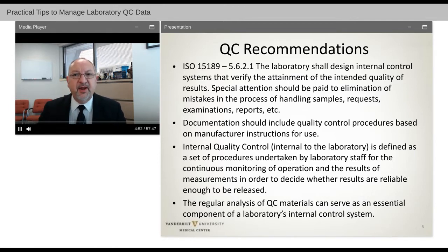Internal quality control, by this definition, is that liquid QC, those processes and analyses that we do in the laboratory that are internal to our laboratory, as opposed to proficiency testing, which I'll describe later in this talk. Internal quality control is defined as that set of procedures undertaken by the laboratory staff for the continuous monitoring of operation and the results of measurements in order to decide whether we release results and whether they're reliable enough for patient care. The regular analysis of quality control materials serves as an essential component of our laboratory's internal control system.